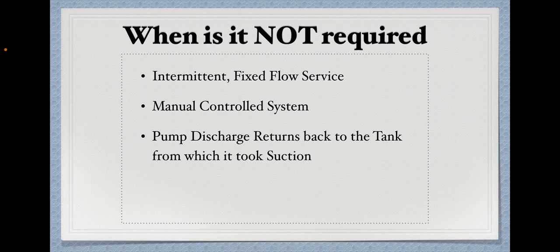When is minimum recycle not required? Minimum recycle lines are not provided in services like tank to tank pump transfer or in loading situations where the flow is fixed and the operation of the pump is intermittent in nature.